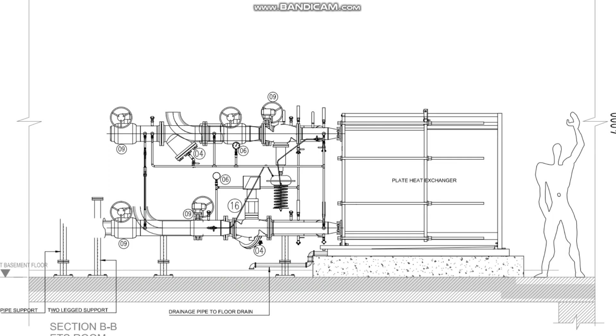So when it comes to the flange side, most of the time we make one mistake that I will explain here. In the chilled water system, the flange connection is one of the very important things, because if you see in the ETS room, for example, there are strainers, and the strainers are joined with the pipeline with the aid of flanges. Similarly, in the ETS room there are lots of valves, motorized valves, manual gate valves, and also flow meters and BTU meters. There are different arrangements, and in all these arrangements we have flanges.